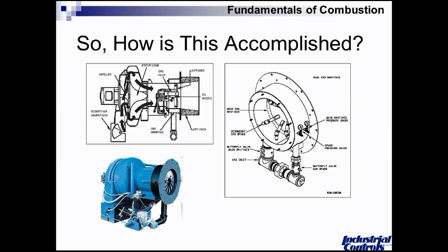The pilot itself is a very small flame in contrast to the main burner. We essentially use a spark in this burner to light a pilot. The small pilot then is used to light the main burner. You can see how each step successfully builds the flame size. Let me ask you a question, and I realize there's not a perfect answer to this question, but if I'm looking at the flame, are there signals, are there tips I can get from the appearance of the flame that helped me understand what's going on? That's a really good question. In years past, a lot was done by eye when fuel was not that expensive. I would never encourage that. I would encourage the use of a combustion analyzer under any conditions because, from my experience, there are some burner designs that are really not suited for a good deal of forward velocity at lower firing rates, meaning we don't have a lot of activity. The blower doesn't develop a lot of static pressure. We don't bust the fuel envelope up very well.